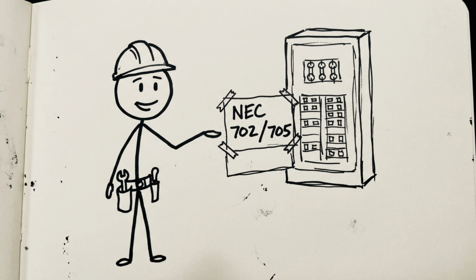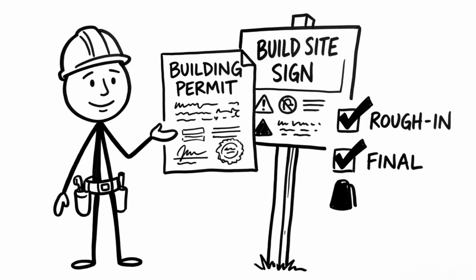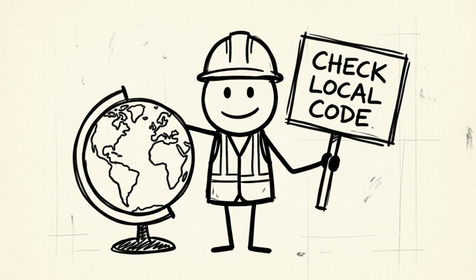This build is governed in the United States by the National Electrical Code, or NEC, primarily Article 702 for optional standby systems, and Article 705 for sources that interconnect with the grid. Every transfer switch must be listed for its use and must use break-before-make switching. A licensed electrician is required to install a battery-based energy storage system and to pull the permit. 2 inspections, rough-in and final, are standard, and the required standby source signage at your main service equipment is not optional paperwork. If you're building outside the United States, the same core principles still apply: break-before-make isolation, a qualified installer, proper signage, but confirm your own country's wiring code and local authority requirements.